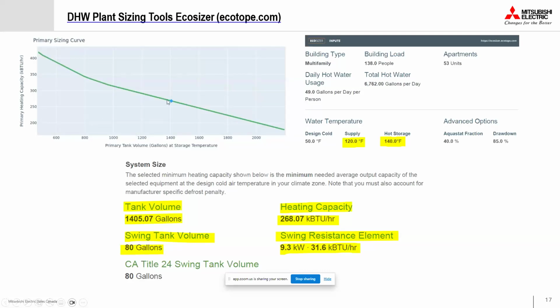The graph on the left is the trade-off between your storage capacity and the production capacity. As I mentioned, if you're designing, you can compromise on that and find where your sweet spot is in terms of energy and cost saving. So if I increase my storage capacity, instead of having 1400 gallons, if I have 2000 gallons, then the production capacity or the heating capacity of the equipment will reduce to only 200,000 BTU.